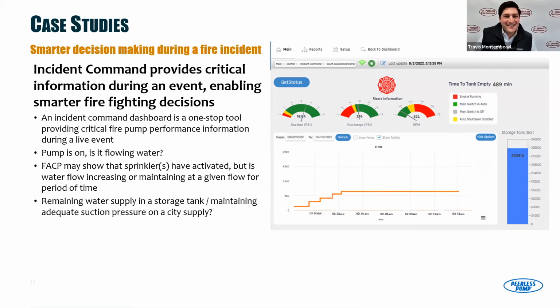Yeah, exactly. So last case study, smarter decision making during a fire incident. So FireConnect has a tool that we call Incident Command. And what that is if that fire pump is running, we are telling you how that pump is performing. So we're monitoring flow from that fire pump, whether it's using an ultrasonic flow meter, so a piece of hardware, or it's monitoring using what we call estimated flow by looking at the difference in pressure against your pump curve. We're able to tell you how much flow is coming through that fire pump. And that's important during a live event, because as you're opening sprinklers, your demand for that system is increasing. And so the fire pump is flowing additional water over time.